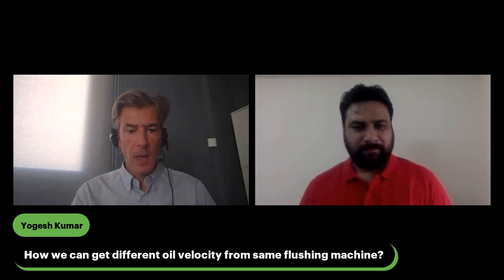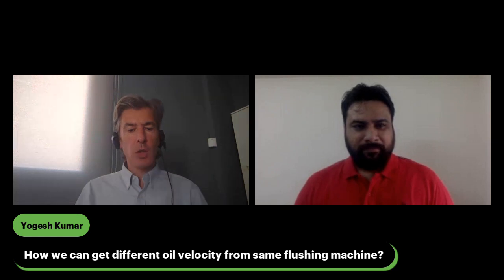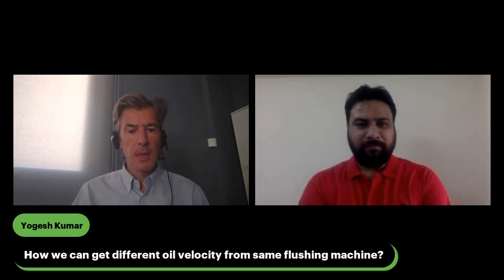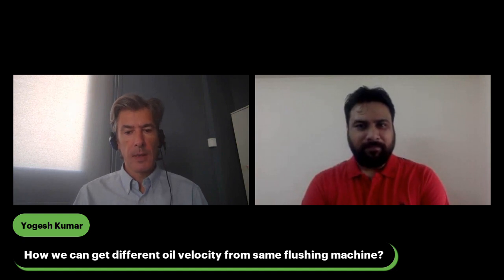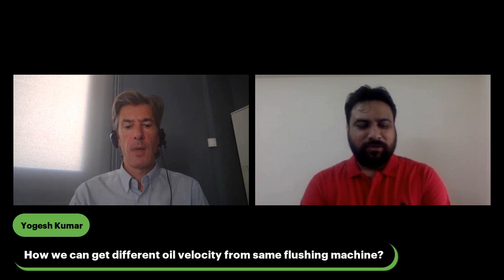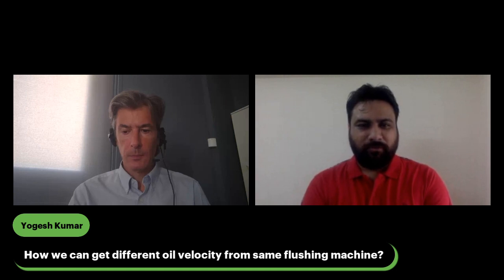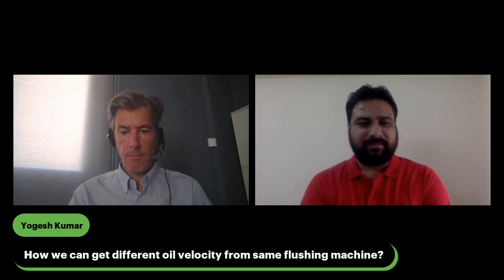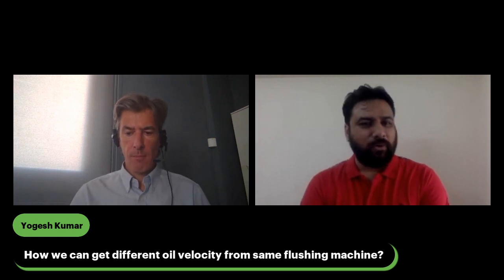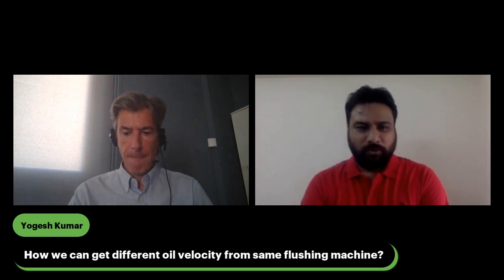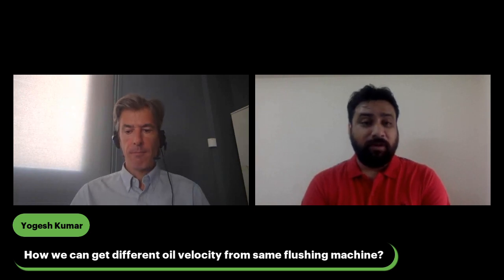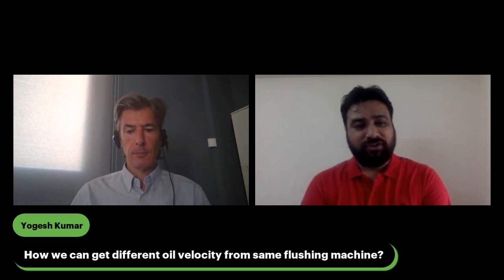Okay, now a question: using the same flushing machine, how do we adjust the oil velocity? Great question. With the same flushing machine, if it's an external flusher, you could actually generate various flow rates. When these flow rates go into various diameters of the loops, they would create different oil velocities. So you could have a manifold system in your flushing machine, and with those manifolds, you could serve multiple loops at a time, generating different flow velocities and flushing flow rates.